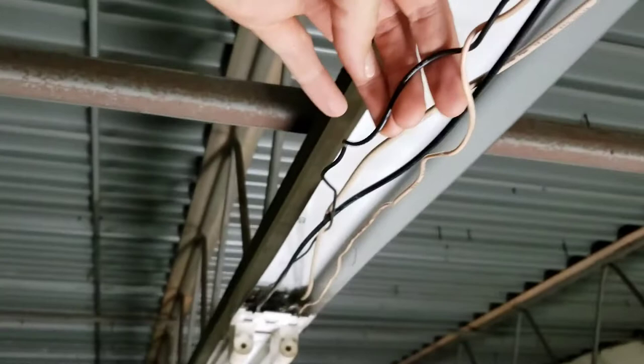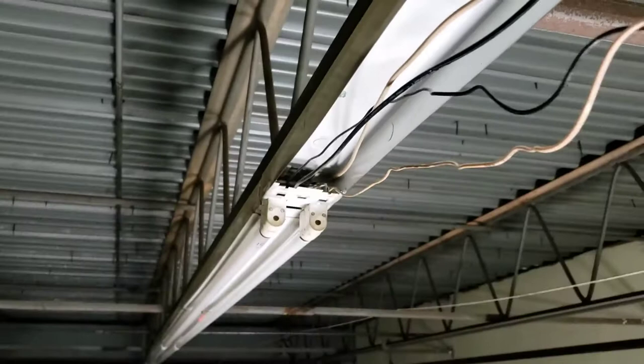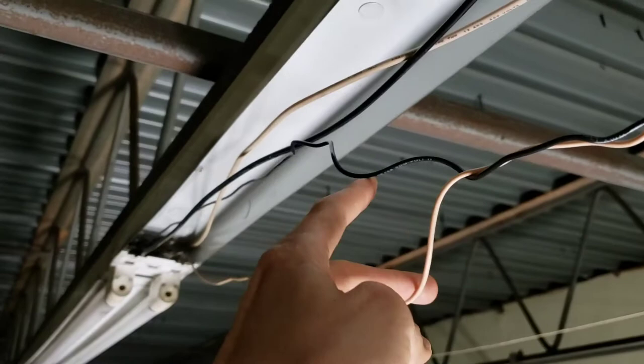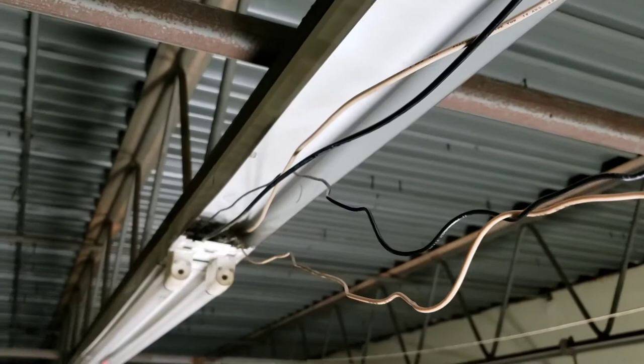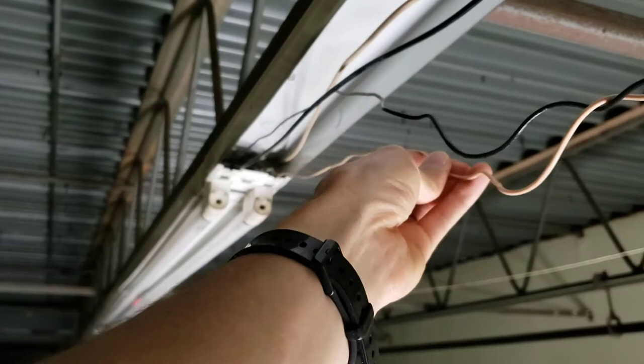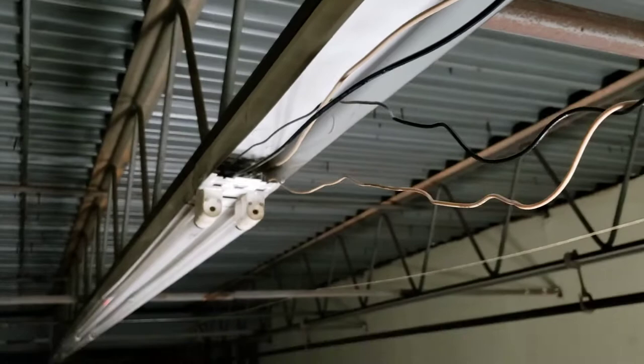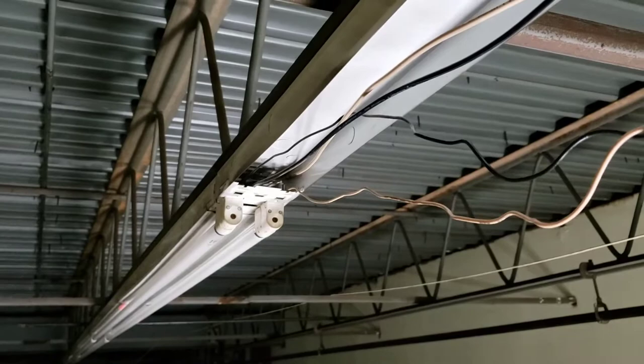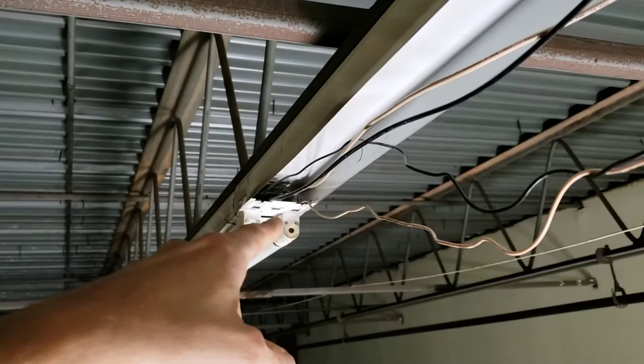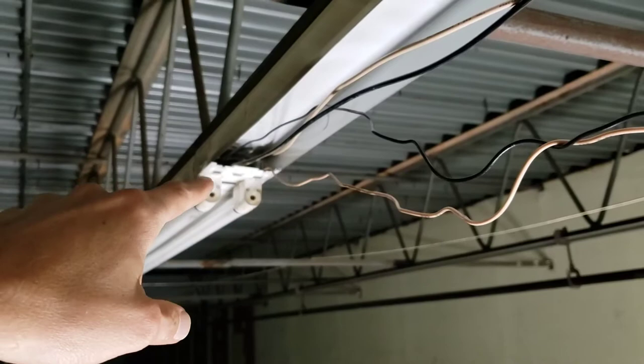At this end we have the black and white wires coming from the connectors at the ends. Something that threw me off is those connectors are also connected to the power. The holes have two contacts in there - one contact is the power coming in, one contact is the power going back out to the ballast. So there will be no power going to the ballast unless the lights are in the fixture. That's a safety feature - you wouldn't actually have to turn off the power to service the ballast, though I don't recommend this.